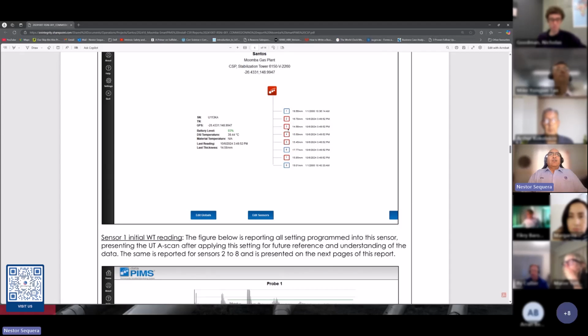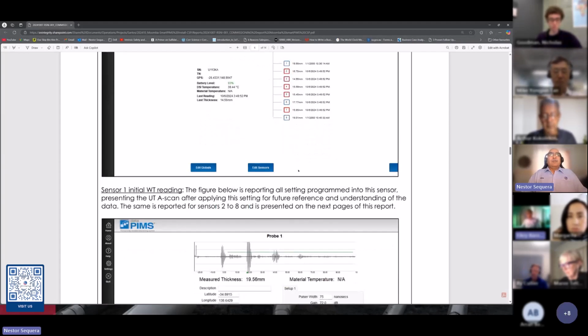As you see, 1, 2, 3, 4, 5 of the 8 sensors were already under the corrosion allowance because they were matching the corrosion monitoring locations that the team wanted us to monitor. And the control units, the 1 and the A, are close to nominal, so they are in blue color. So this is how the system is already giving you updates.